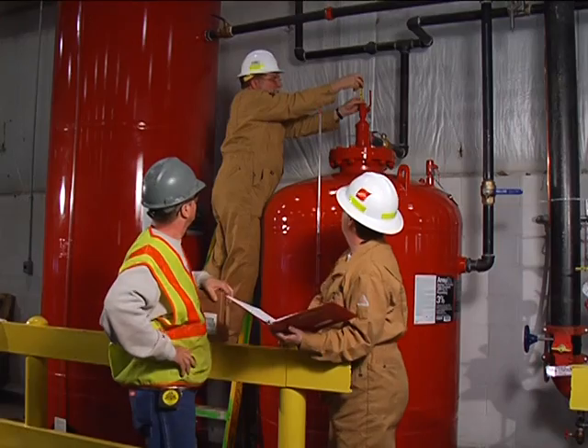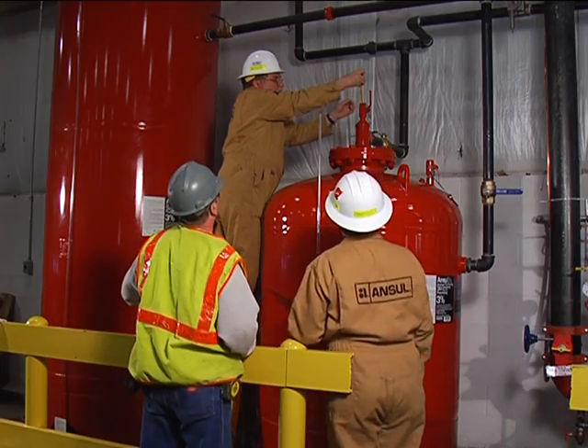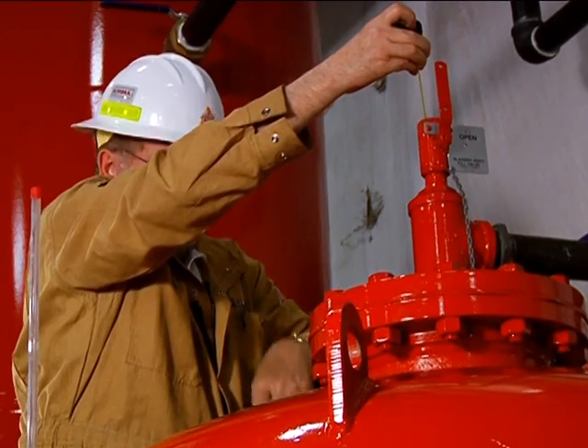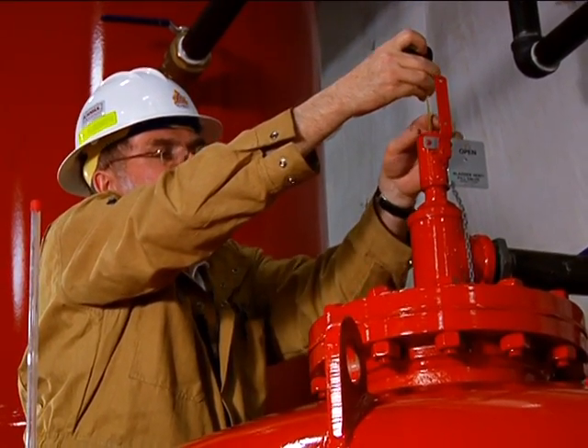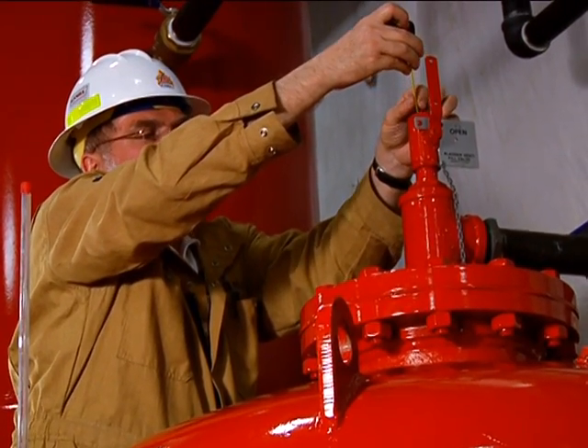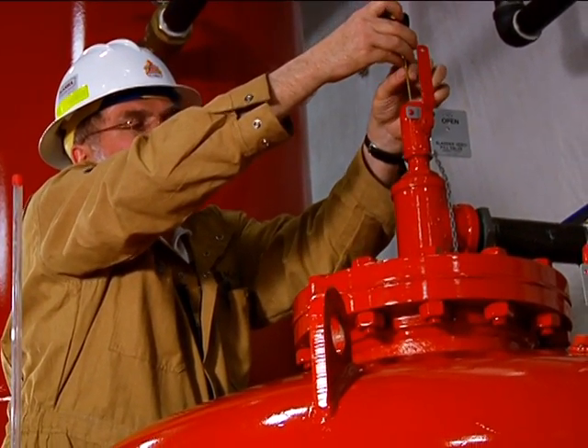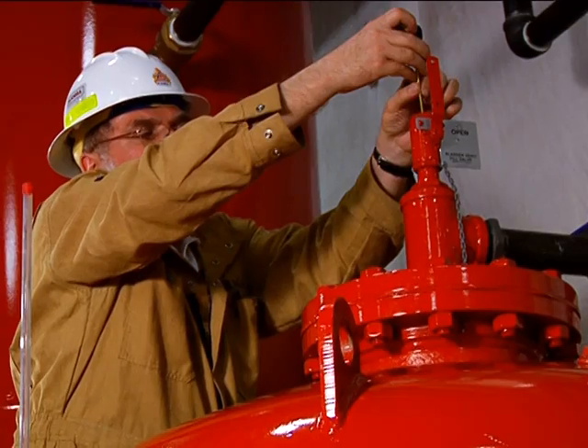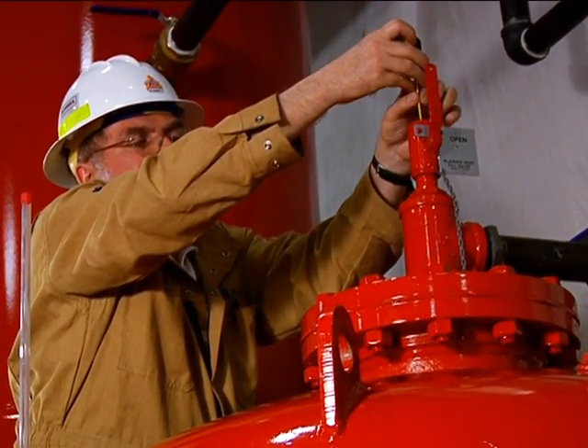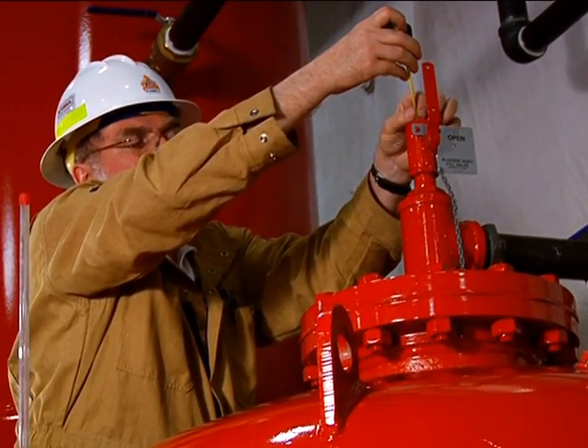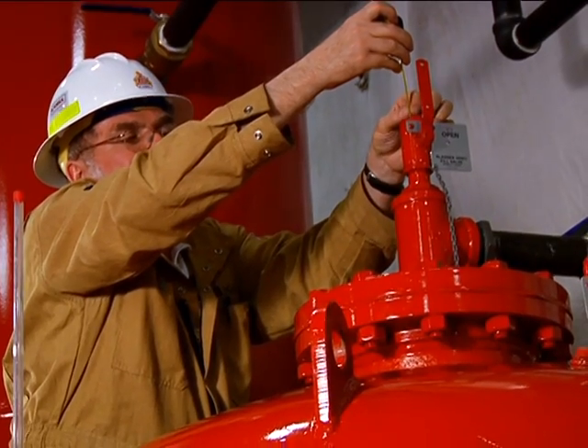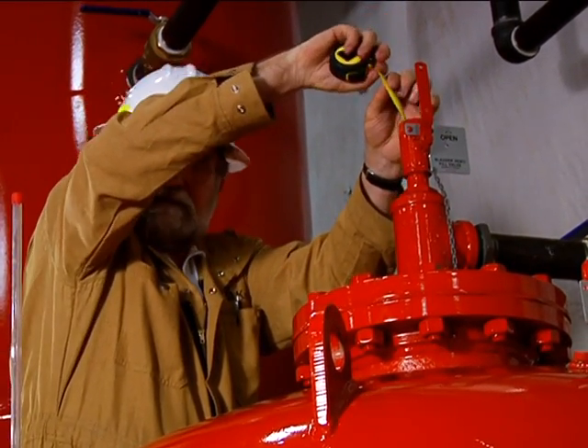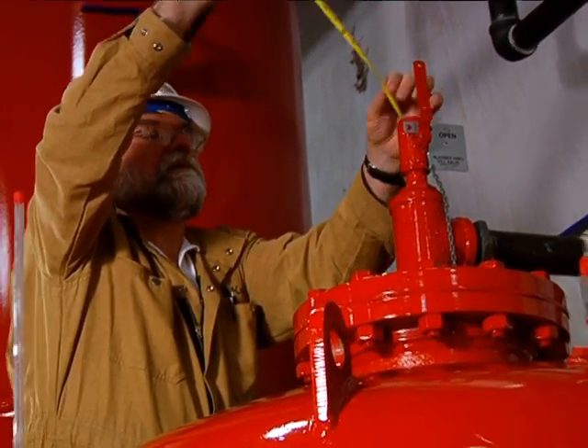Okay, right now we have the tape measure right down till it hits the bottom flange at the bottom of the tank. Now, if I retract the tape measure slowly to see where it's wet, what I'm feeling for here is for when the tape measure gets wet. Okay, it's wet right here. Looks like it's about 54 inches. And we said 53 and a half before, didn't we?